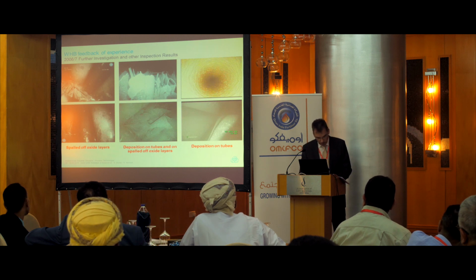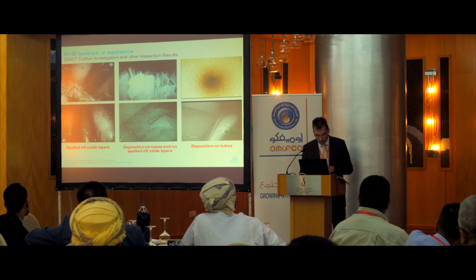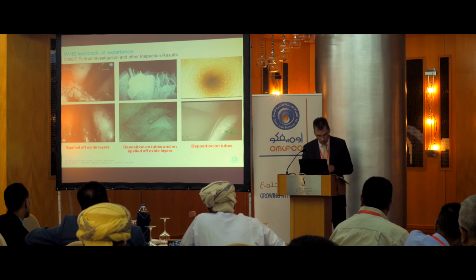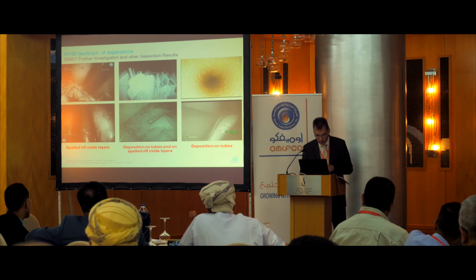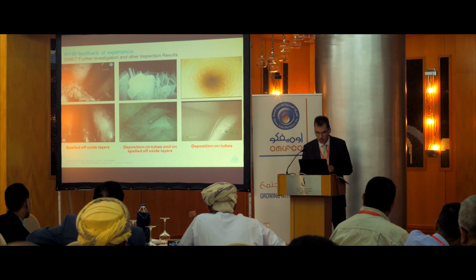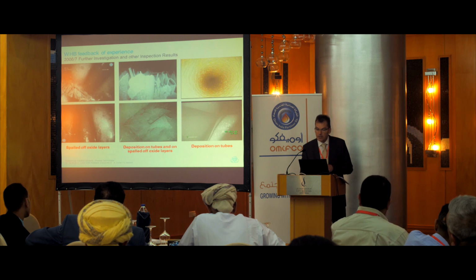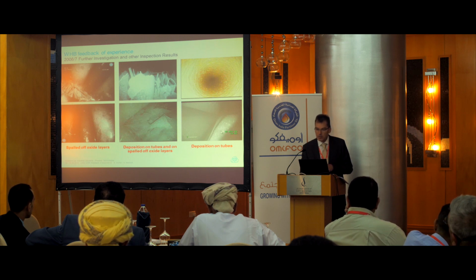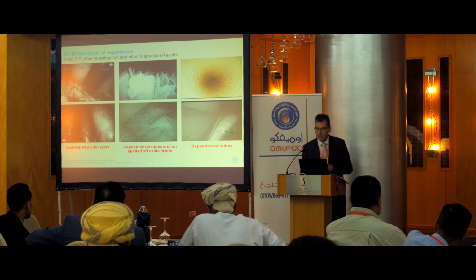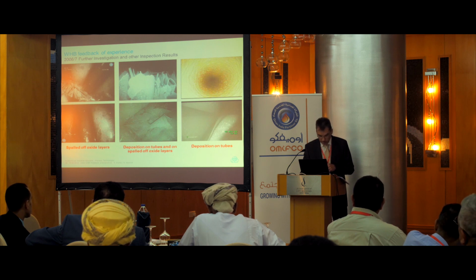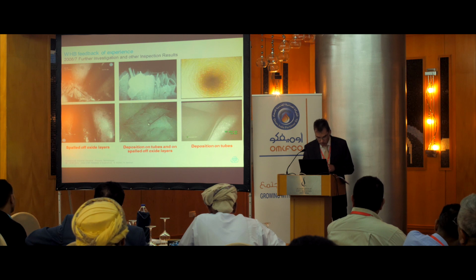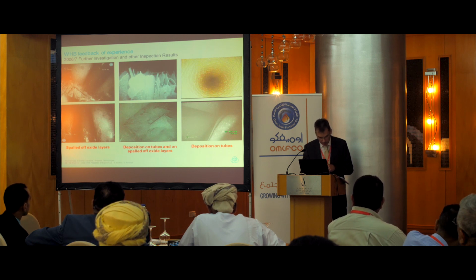Second source: porous oxide layers can also be formed by deposition on tubes and other iron parts, where dissolved iron in the liquid gets deposited on porous magnetite, which appears as a sparkling surface. When this happens and you look inside the boiler with the borescope, you see some sparkling effect. This is due to the light of the borescope, of course, but it is an indication that something is wrong with the boiler feed water. Some iron is in the boiler feed water, which will be deposited. Also, a combination of both effects is possible, as seen in the center photo. The two photos show spalled off oxide layers, here and here, with additional deposition of magnetite on these oxide layers.